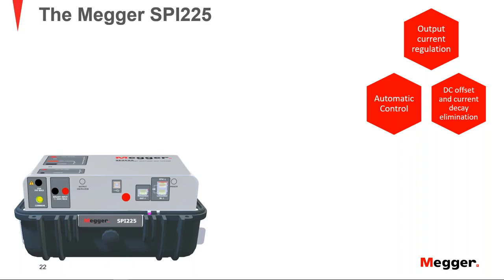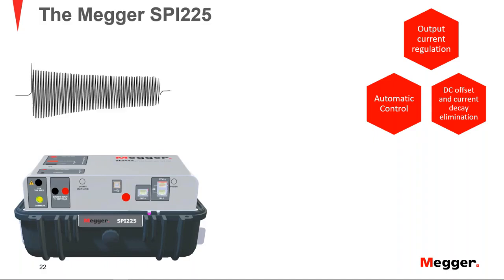And most importantly, the current regulation is automatic, right? For those that have performed these tests in the field, you know that we face a phenomenon called current decay. When we make our first measurement on a circuit breaker, we have to determine the peak value. Let's say we need 700 amps. In a traditional instrument, we have to find that point in the adjustment of the output where the unit will deliver the 700 amps for that particular configuration, with the impedance that I'm connecting to the instrument. So I start my test, especially when I'm testing overload and those long time delays. The current will be injected for several seconds. And given the nature of the test itself, we are using high current.